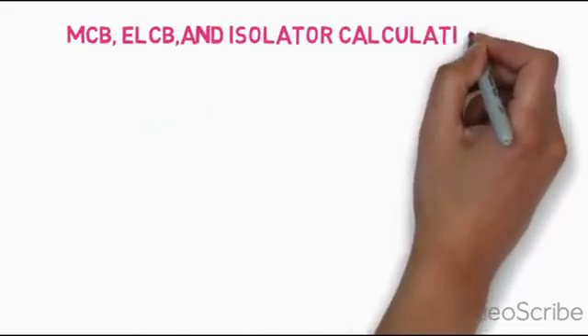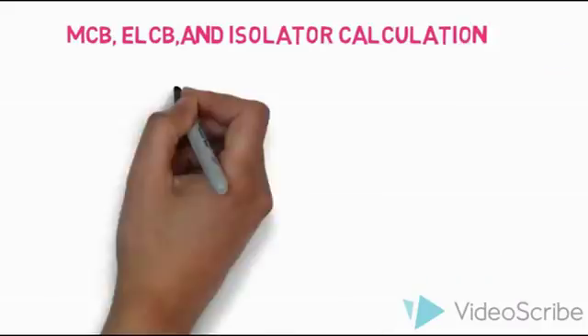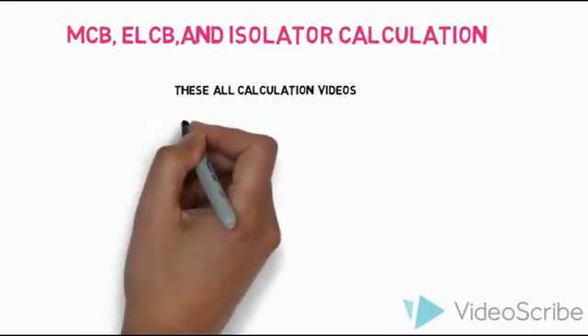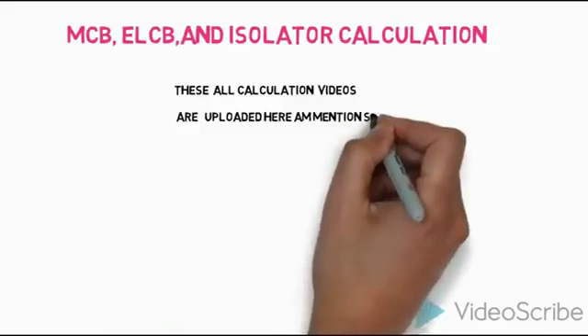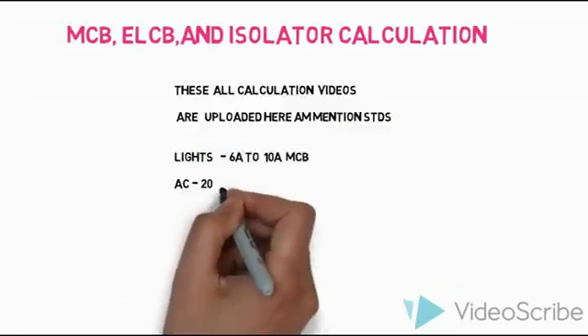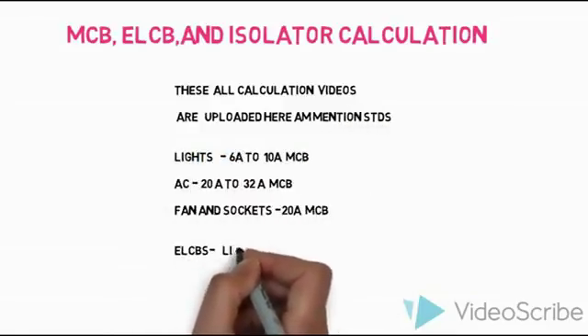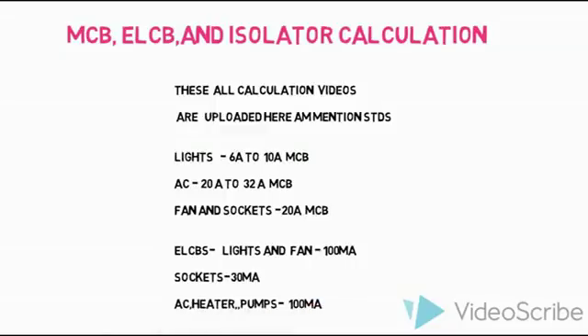Now we fix the MCB, ELCB, and isolator ratings. For ELCB: the light and fan circuit is 100mA, the general circuit is 30mA, and the AC and heater circuit is 100mA. If you want to use an isolator, you can install one accordingly.